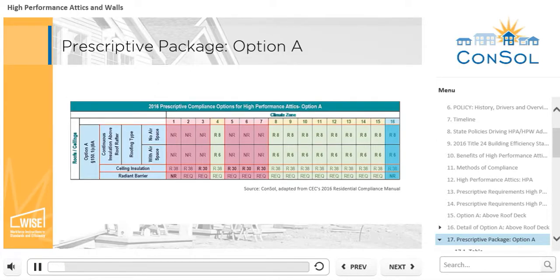This table represents the 2016 Prescriptive Compliance Requirements for Option A. Highlights of the requirements include a ventilated attic, R6 when there is an air gap, R8 when there is no air gap, a radiant barrier, and, for most climate zones beyond the coast, R38 is required above the finished attic ceiling. Click on the table to enlarge.